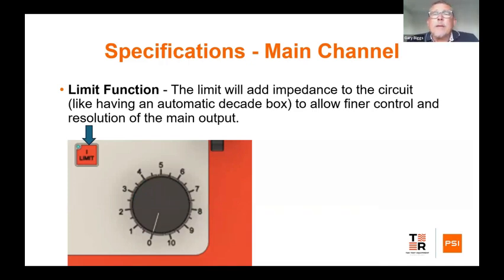Now, one of the things I mentioned is relays themselves have changed over the years. As I said, the older electromechanical relays had quite a burden to them. So if you use a little 30 VA unit to try and inject a current into there, you won't be able to do it. You'll probably blow your test set up because it won't be powerful enough. And traditionally, the more powerful relay testers were too powerful, and there was not enough finesse.